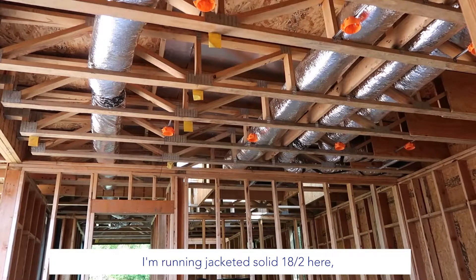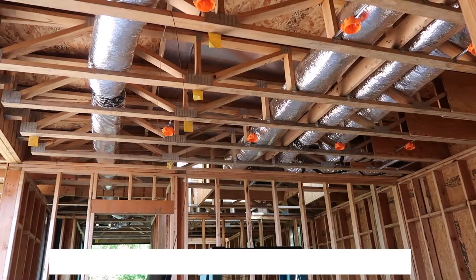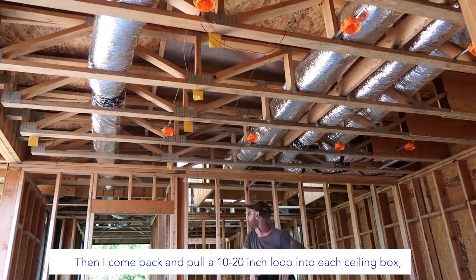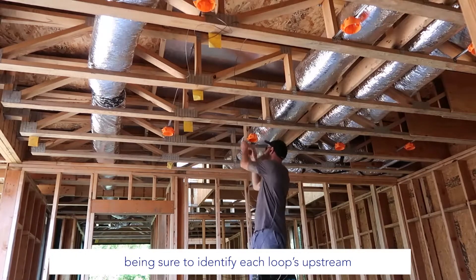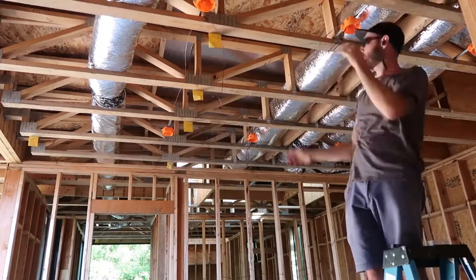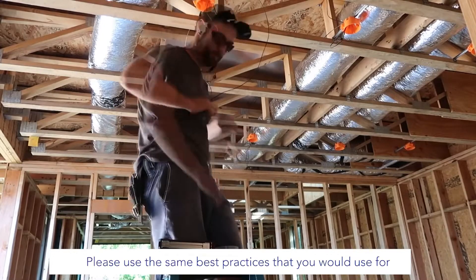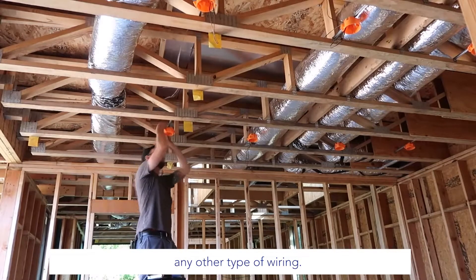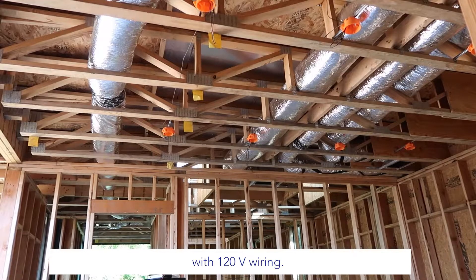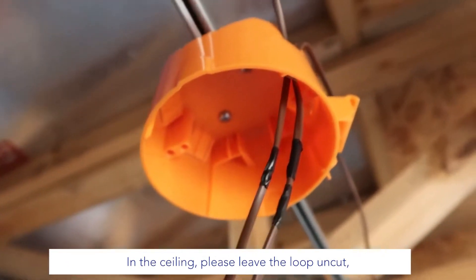Time to start with wire. I'm running jacketed solid 18-2 here, but jacketed AWG 20-2 is also acceptable. First, I'm finding a comfortable path for all the wire, making sure I have plenty of length. Then I come back and pull a 10-to-20-inch loop into each ceiling box, being sure to identify each loop's upstream and downstream ends with tape or by following the sticker. Note that it is the installer's responsibility to correctly pull the wire — please use the same best practices you would use for any other type of wiring. Never use aluminum wire, avoid sharp edges, and don't share any holes in wood with 120-volt wiring. Use the wire marking method at the wall box for up and down loops, and in the ceiling please leave the loop uncut.